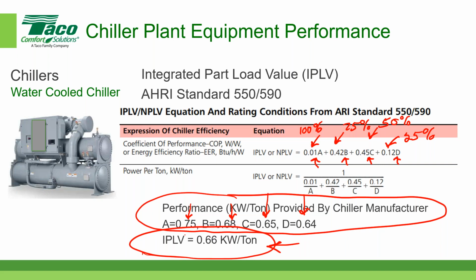So the IPLV, again, stands for Integrated Part Load Value, and it's a standard established by the American Heating and Refrigeration Institute. It's not necessarily what your chiller plant is going to operate at, but it's kind of like the sticker on the window of your car that says here's the highway mileage, here's the city mileage, and here's the combined mileage per gallon. It's not what you're going to get when you buy a car, because you're not driving your car based on that standard. So this is a standard by which chiller manufacturers can compare them.